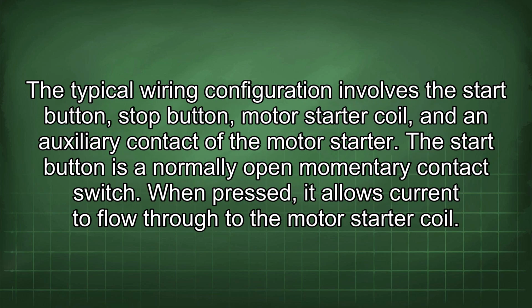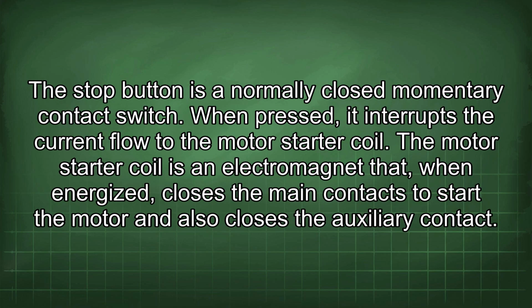The typical wiring configuration involves the stop button, motor starter coil, and an auxiliary contact of the motor starter. The start button is a normally open momentary contact switch. When pressed, it allows current to flow through to the motor starter coil. The stop button is a normally closed momentary contact switch. When pressed, it interrupts the current flow to the motor starter coil.